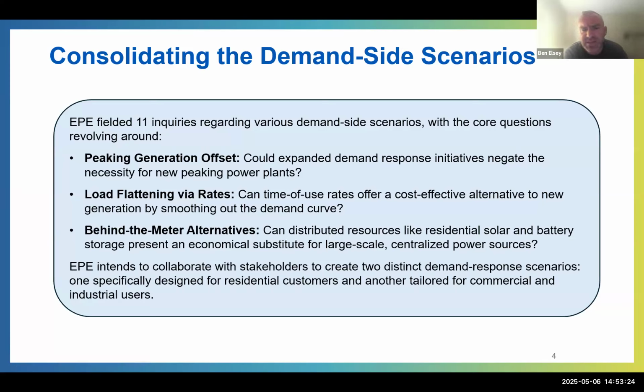The categories were demand response—if you expanded demand response programs, could you offset the need for new peaking gas generation? Second, if you implemented time of use rates, offering incentives for customers to shift usage from peak to off-peak hours, could you improve the load factor and avoid the need for peaking resources? And third, behind the meter alternatives such as residential solar and storage, with additional demand response embedded within those scenarios.